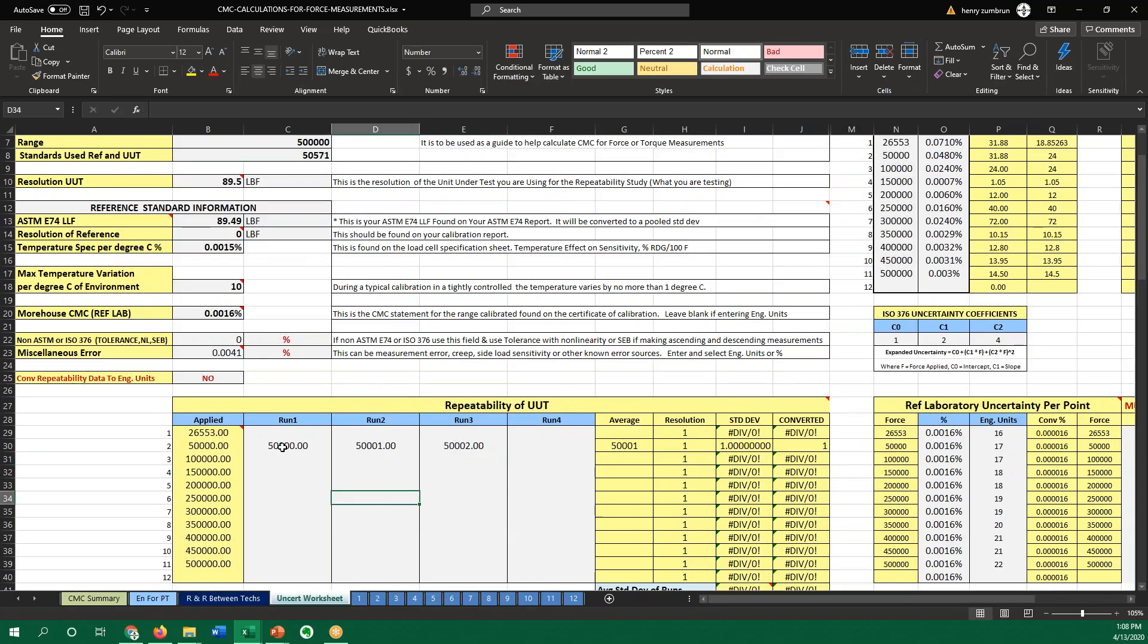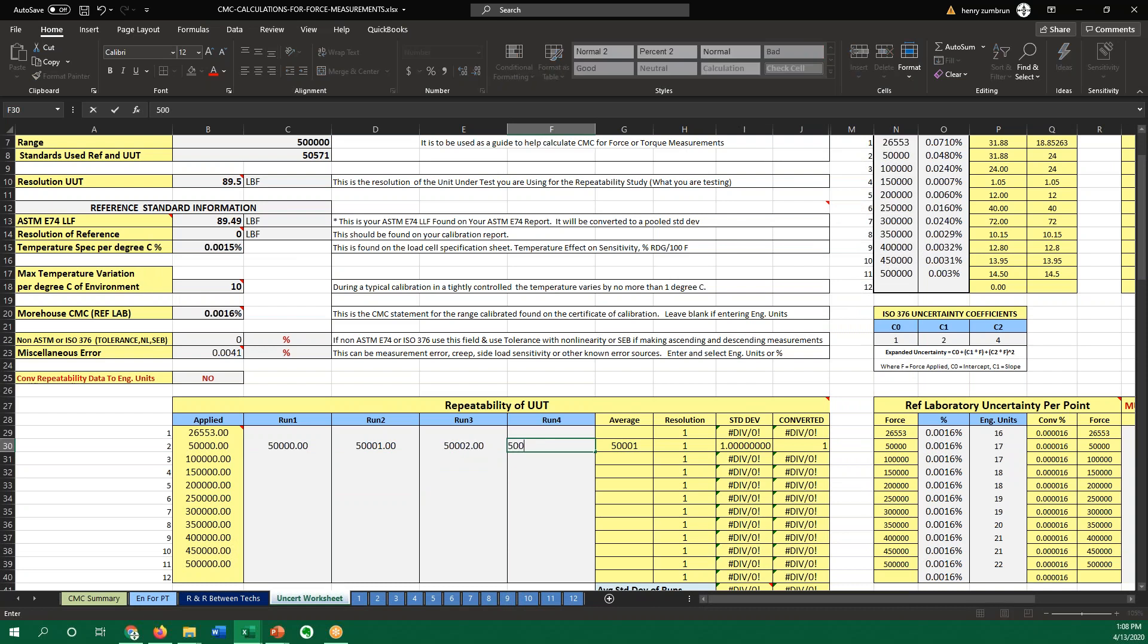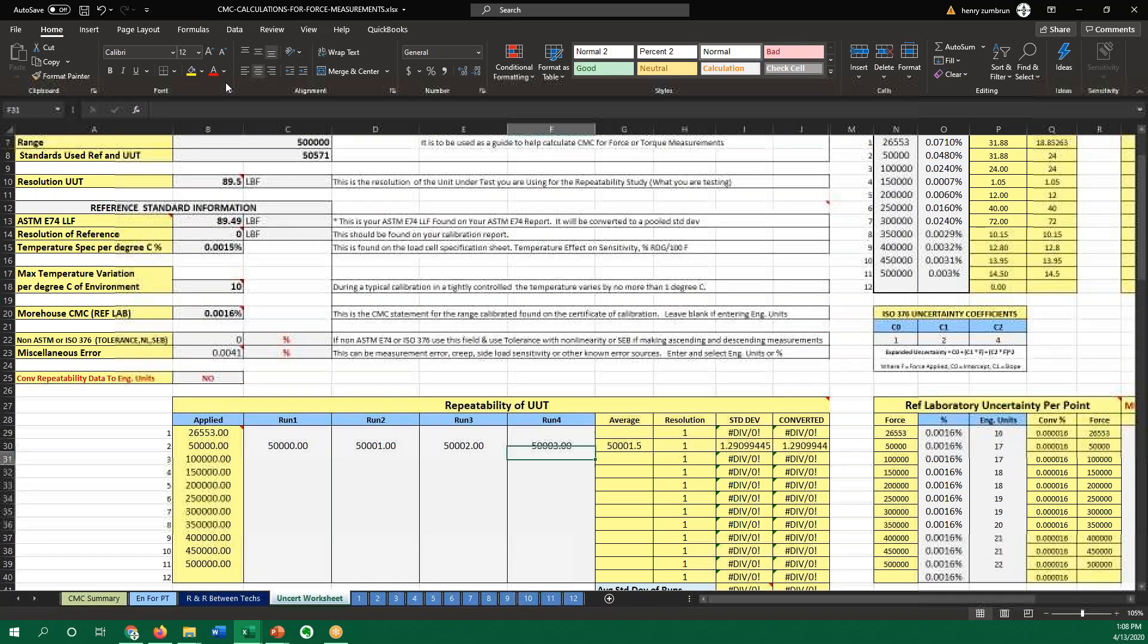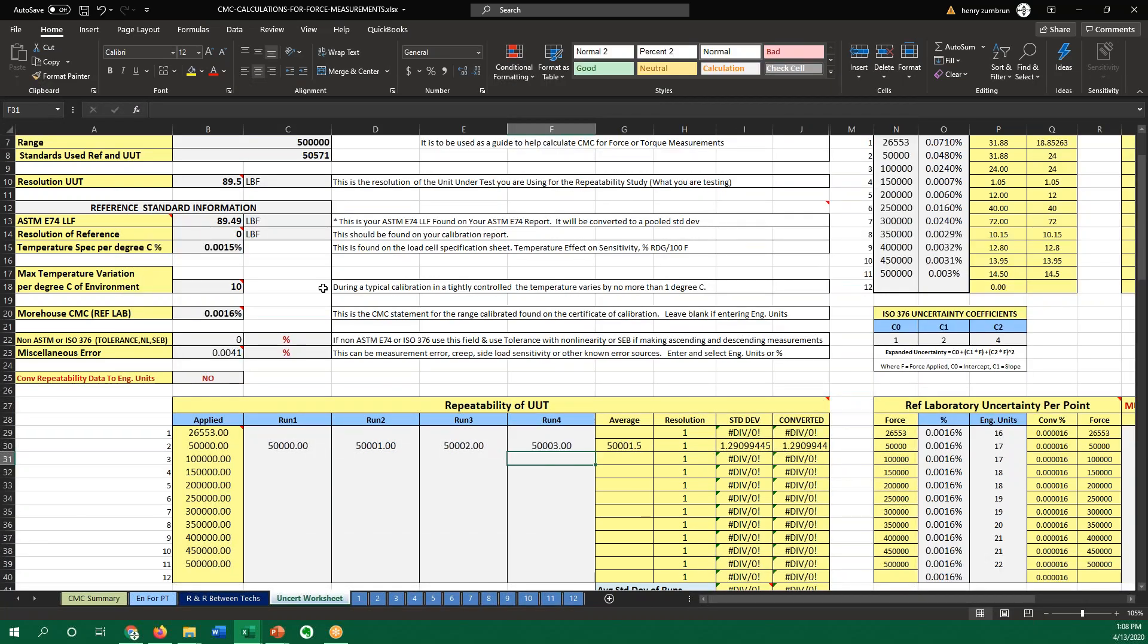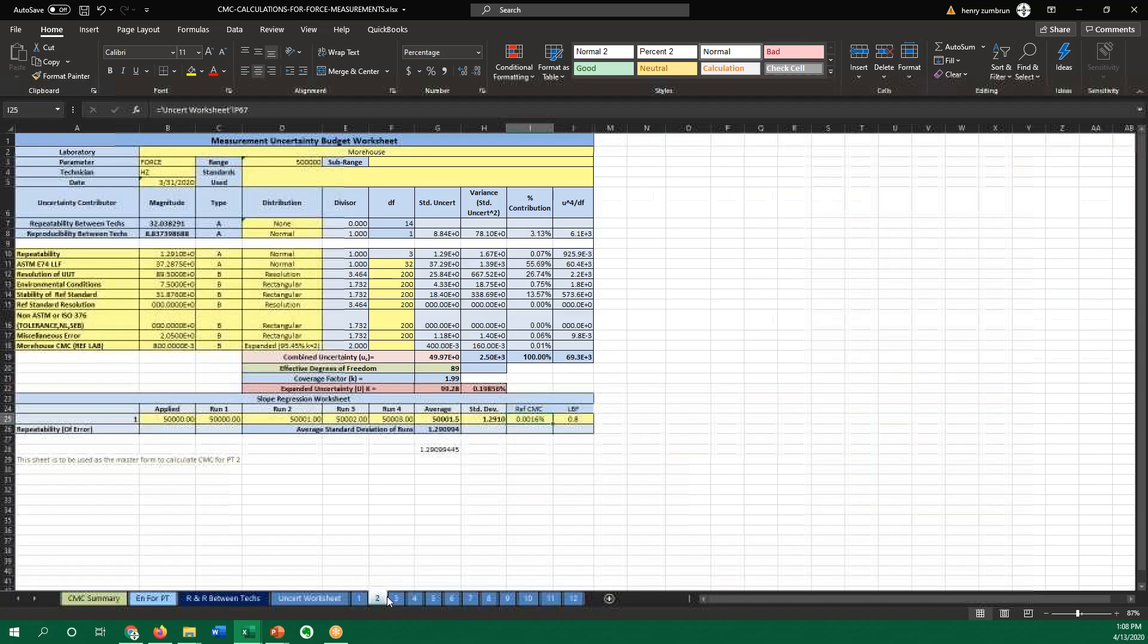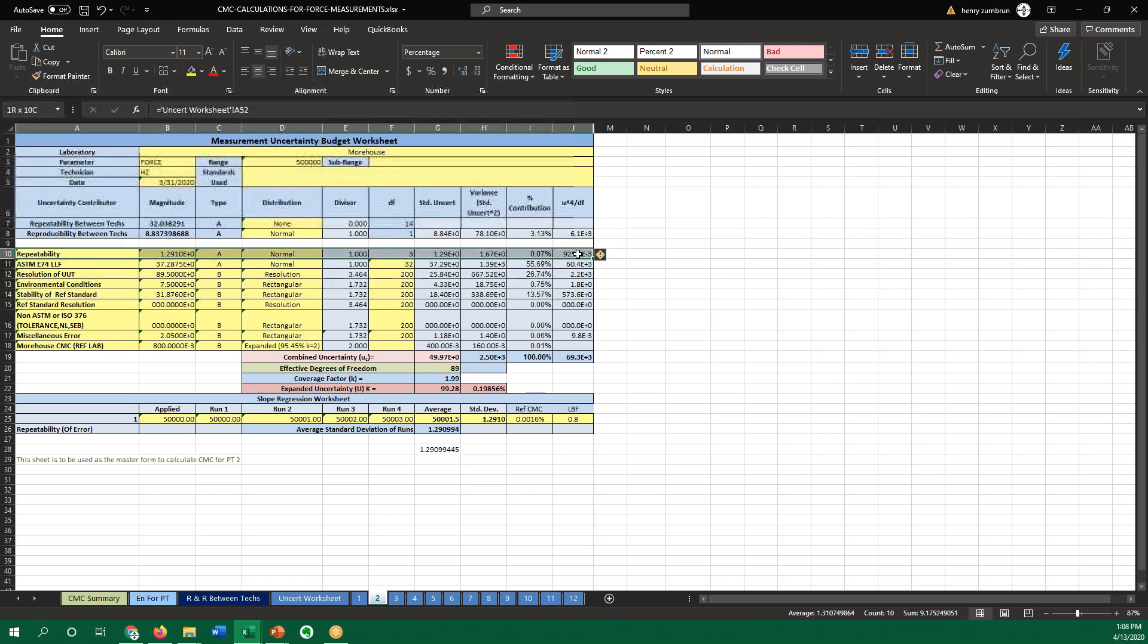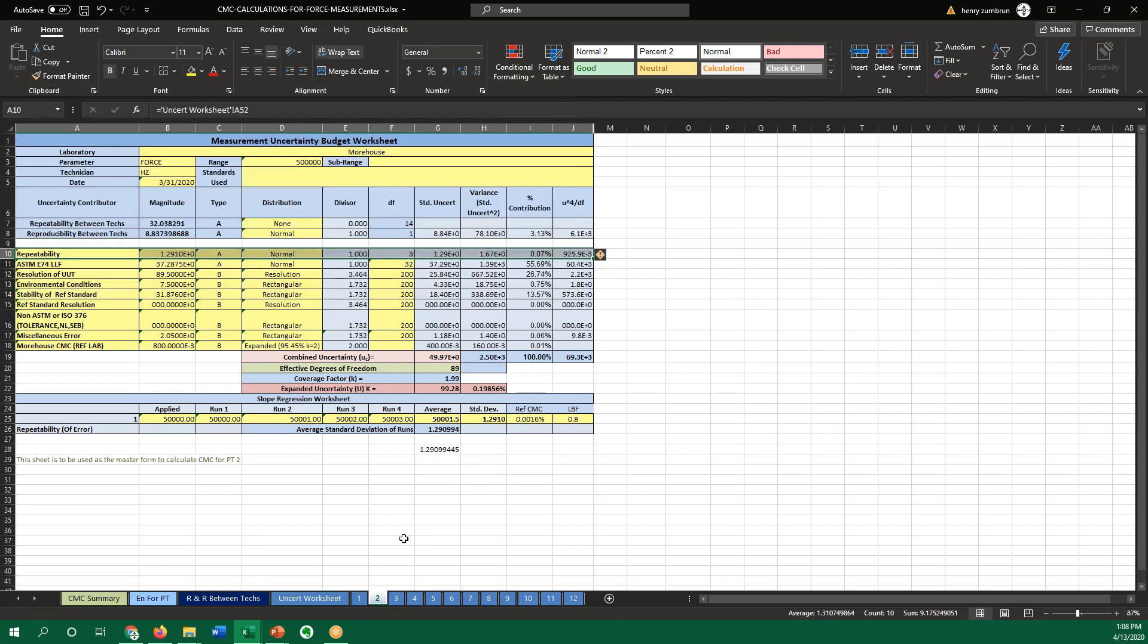So in this case, you can look at repeatability, same thing as that's being done on the other sheet, except for we're doing it, in this one, we're using a range per point. So we would do repeatability per point over the whole range, and this sheet will show different numbers. Here's repeatability contribution percentage-wise.